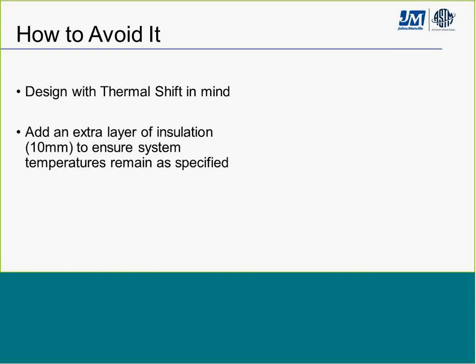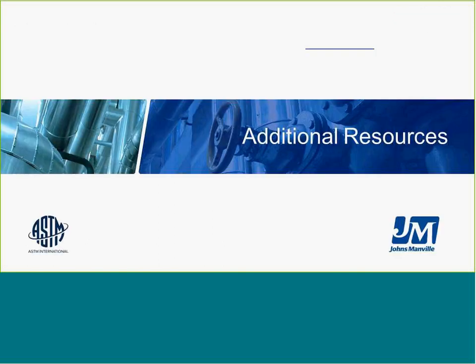To avoid the thermal shift problem, you want to design with that shift in mind. Generally, you can add an extra layer of insulation — in most cases, 10 millimeters would probably do it — but you should refer to the manufacturer's recommendations to ensure you're getting the thermal performance you need. With that, Doug concluded his section, turning it back over to Kim to talk about additional resources.